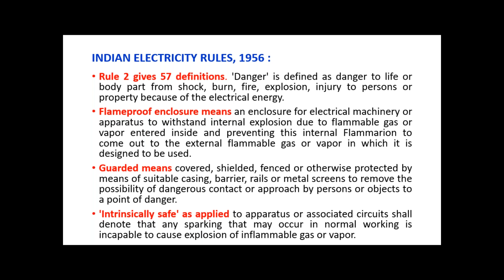Then intrinsically safe, as applied to the apparatus or associated circuits, shall denote that any sparking that may occur in normal working is incapable of causing explosion of inflammable gas or vapor. That is why it is called intrinsically safe. It is especially for the sparking possibilities related to an inflammable gas or vapor environment. We have to avoid the sparking, we have to avoid the ignition source, and we have to avoid any type of heating element near the inflammable gases or vapors.